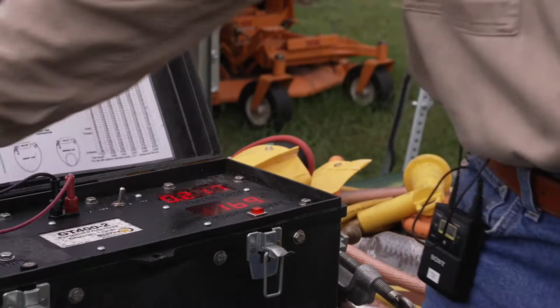So these TPGs, this assembly from start to finish, passes. Some utilities recently, Ryan Bierer has seen, were testing from ferrule to ferrule and removing the clamps for their testing. You can't do that. The linemen are out there using the entire assembly, so you've got to test the entire assembly all put together.